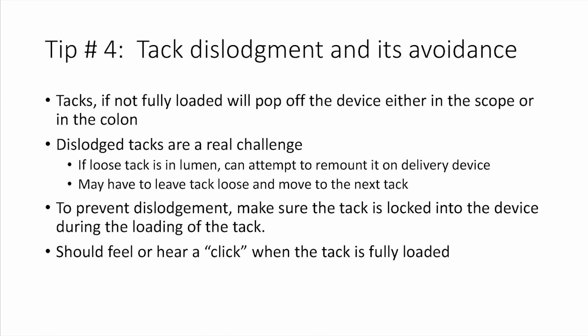If the tacks are not locked into the delivery device, they may pop off the shaft and dangle loose on the suture. If this happens with the first tack, the entire scope can be removed and the tack manually reloaded. If it occurs after a tack has been placed, an attempt can be made to redock the tack in the bowel. If successful, it may be possible to manually screw the tack into the wall. The alternative is to leave the loose tack and move on to the next one. This mishap can be avoided by making sure the tack is locked onto the delivery device before insertion. There is a palpable click that occurs when fully seated.